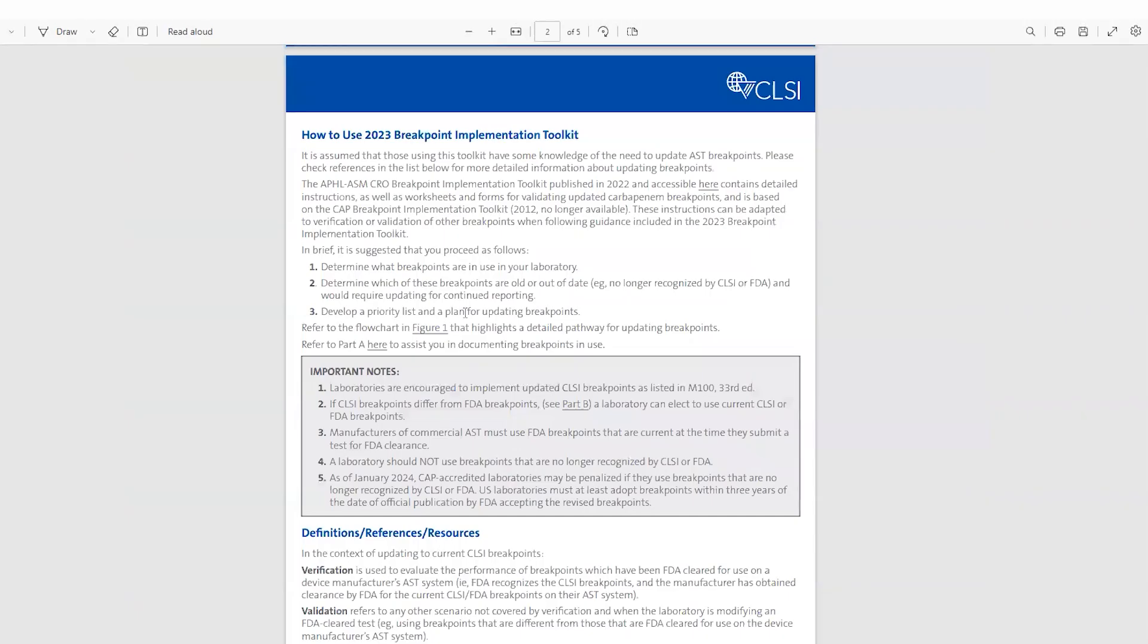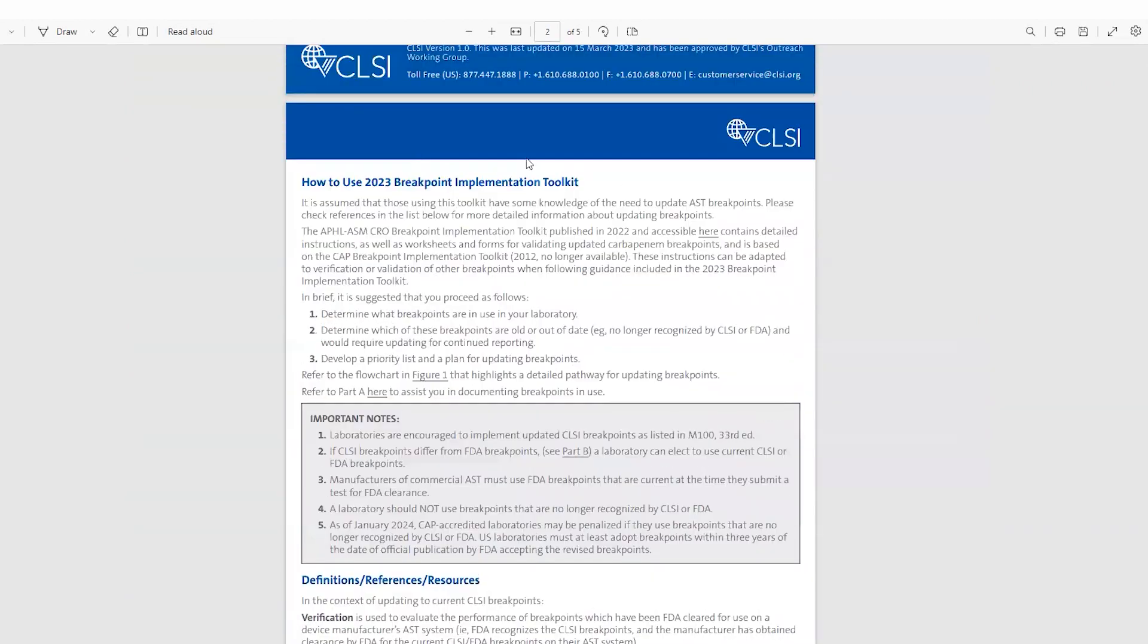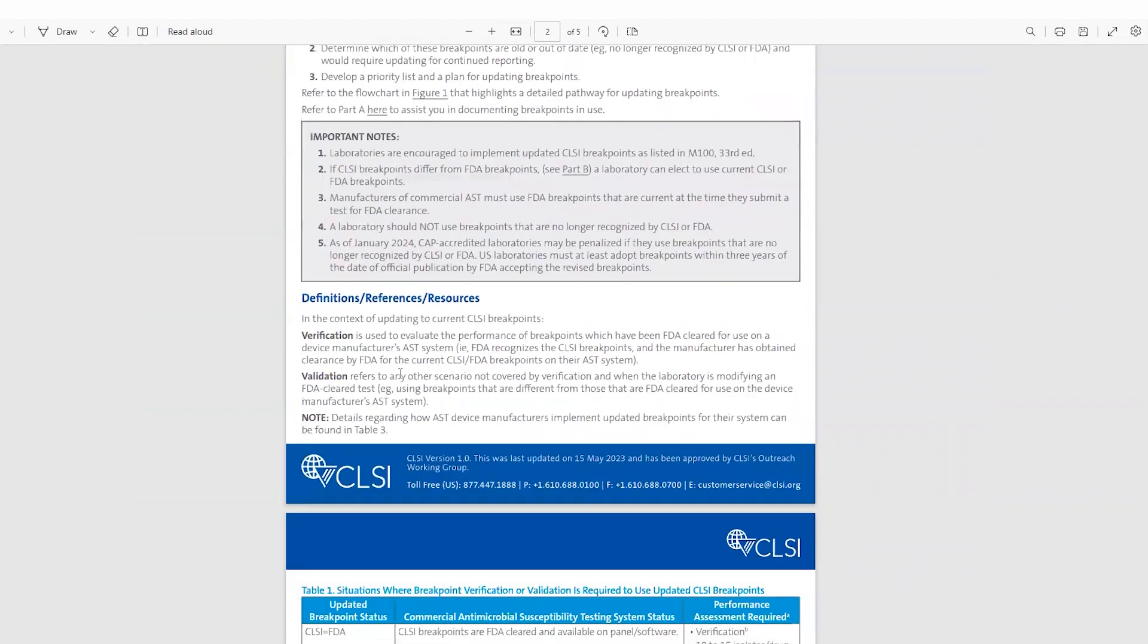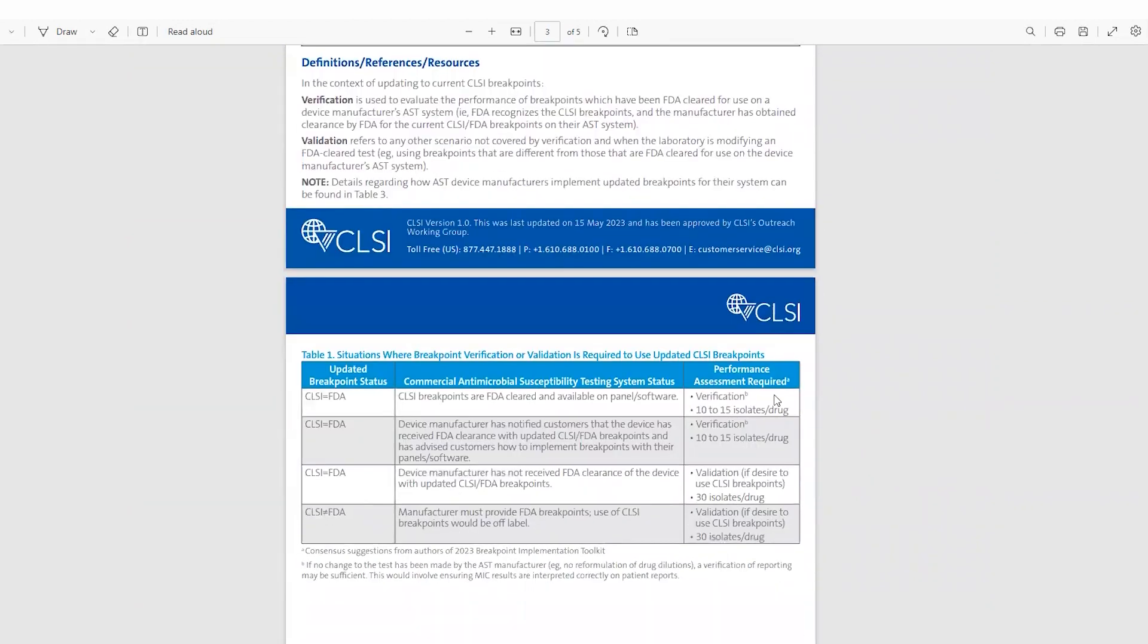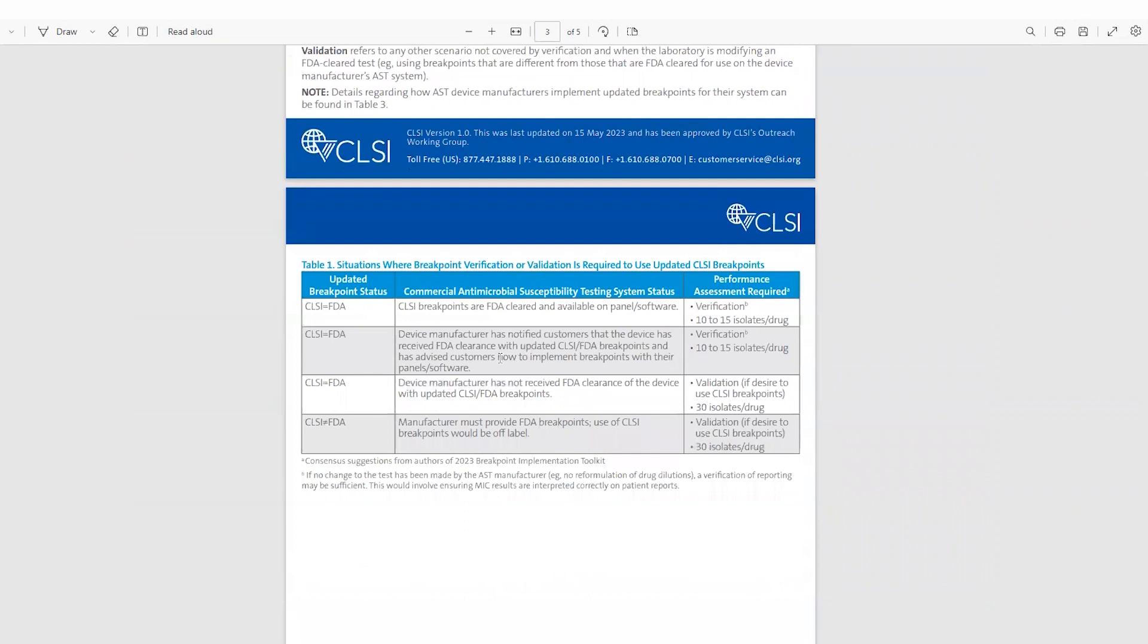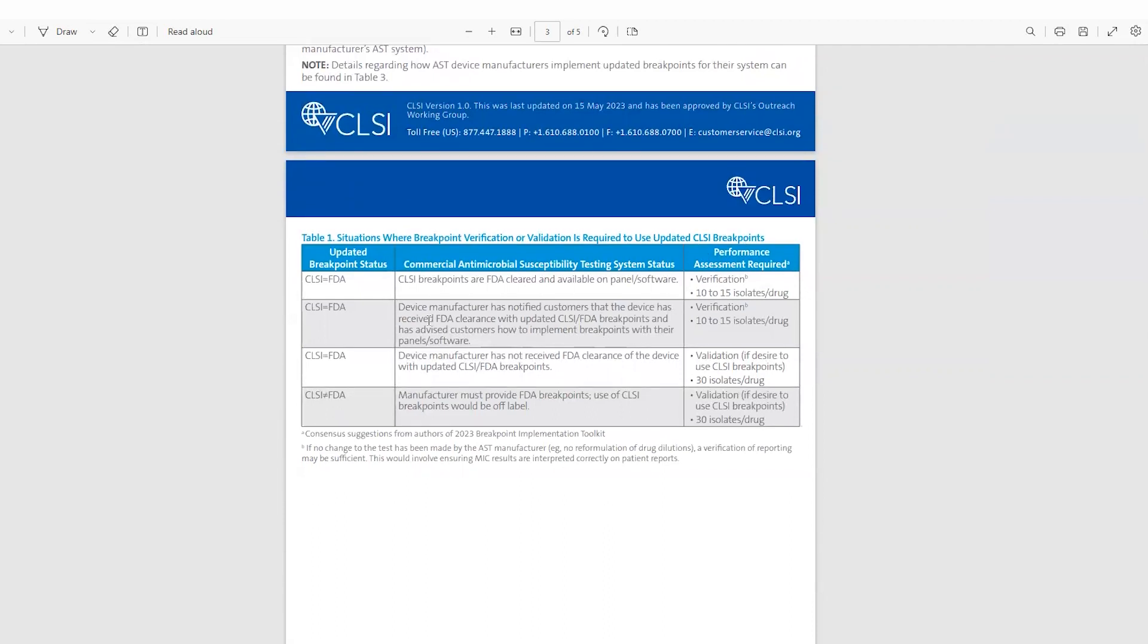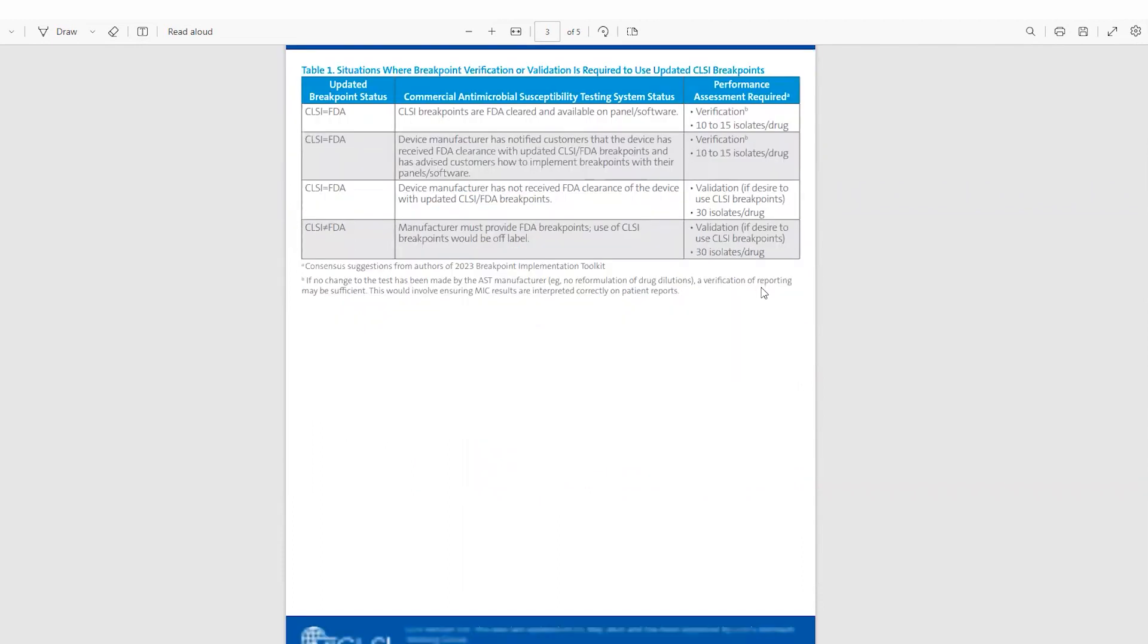Going back to the introduction itself, in addition to instructions for use, there's also some important definitions such as verification and validation. And this nice table that breaks down the situations where breakpoint verification or validation is required to update to use updated CLSI breakpoints. It breaks it down by the status of the breakpoints, the status of your commercial AST device, and the type of study required, whether that be a verification or a validation, and the number of isolates to include within those studies.